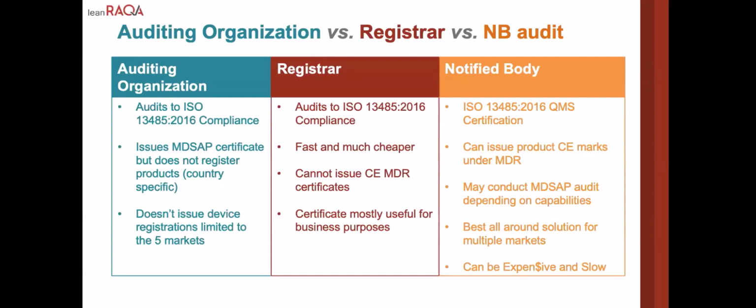And this may be the best all-around solution for multiple markets, if you can find a notified body that's also an audit organization, and you can knock all those out with maybe just one extra audit day. Problem is that notified bodies can be quite expensive and slow. And right now with MDR, the notified bodies are extremely resource constrained, and so it's really hard to get on their dance card.